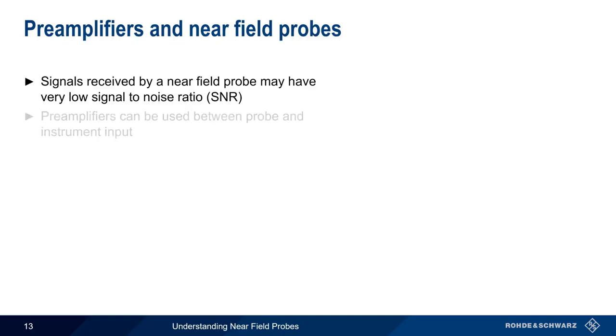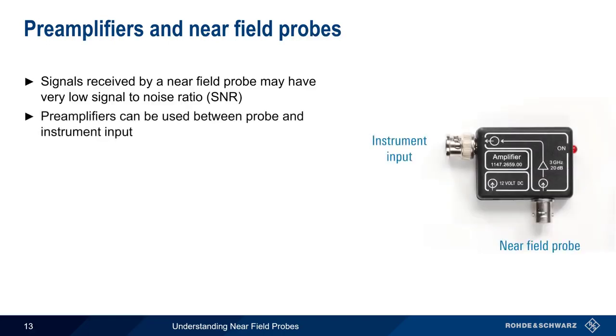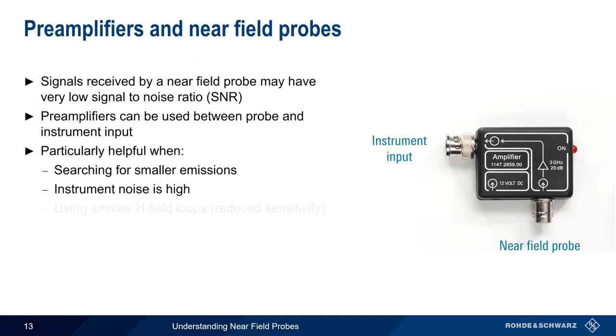One final topic we need to cover is preamplifiers. A signal received from a near-field probe may have a very low signal-to-noise ratio. Therefore, preamplifiers are sometimes used between the near-field probe and the instrument input in order to increase the received signal level. Preamplifiers are particularly helpful in three cases. The first is when the level of emissions is very low. The second is when the oscilloscope, spectrum analyzer, or receiver has a high level of internal noise. And the third case is when using smaller H-field loops, since the smaller loops have reduced sensitivity.